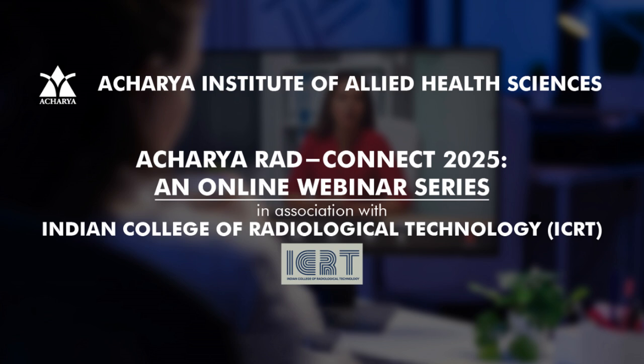What is the MAS and KVP used in low dose CT scan? KVP always depends on the patient. It is not exactly fixed. If a lean patient comes, you can use 80 to 100 kV, and 80 kV also can be used if a very lean patient or a pediatric patient comes. Whereas in normal low dose CT scans, KVP is always 100. MAS is not constant for any CT scan. MAS continuously changes throughout the CT scan.